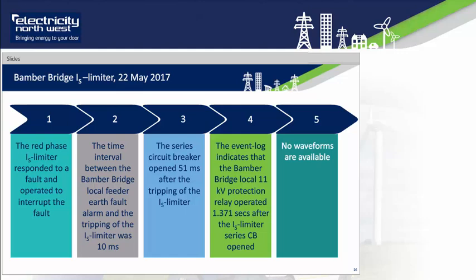The series circuit breaker opened in 51 milliseconds after the tripping of the IS limiter. And the event log indicated the Bamber Bridge local 11 kV protection operated in 1.371 seconds, so it did operate correctly.